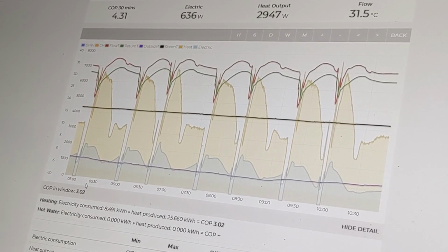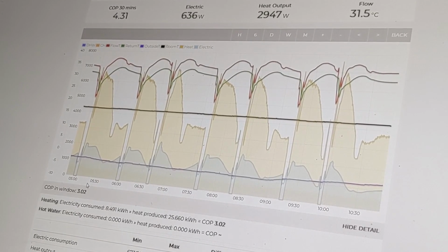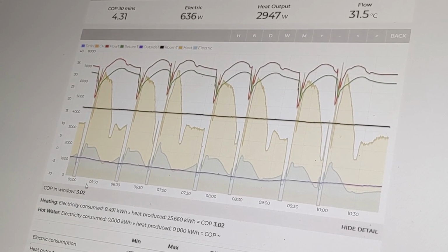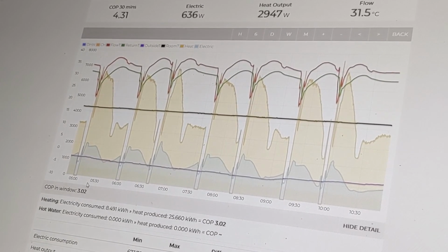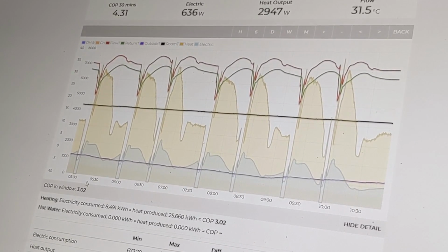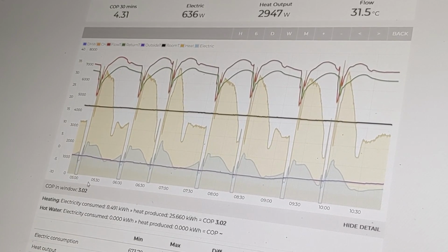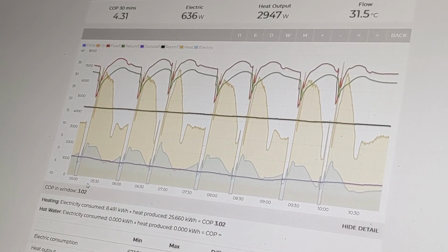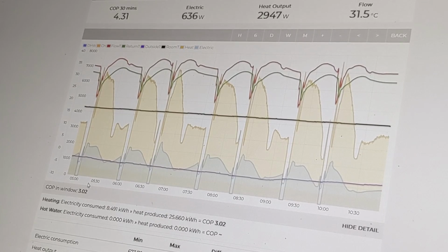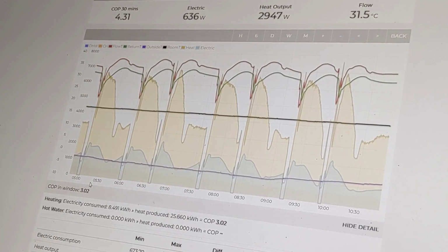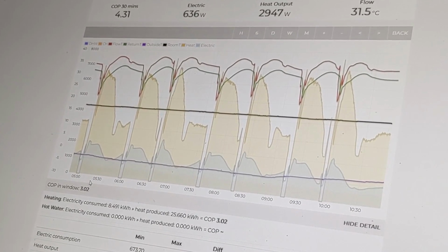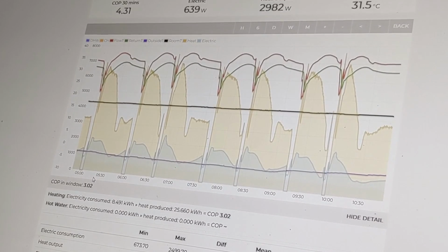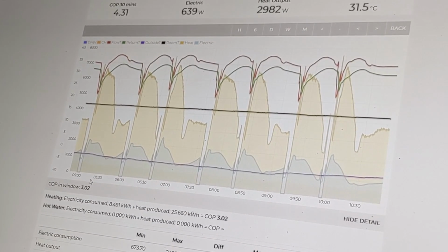So it's almost better to have radiators that are too big for your system than to try and go for exactly the right size. That's right. In all honesty, there isn't such a thing as too big. The thing is to have them balanced so that one room doesn't get very hot and another one cold. But the bigger you can comfortably make your emitters, using, say, underfloor heating, the better. You can then drop your design temperatures and have a more efficient system.